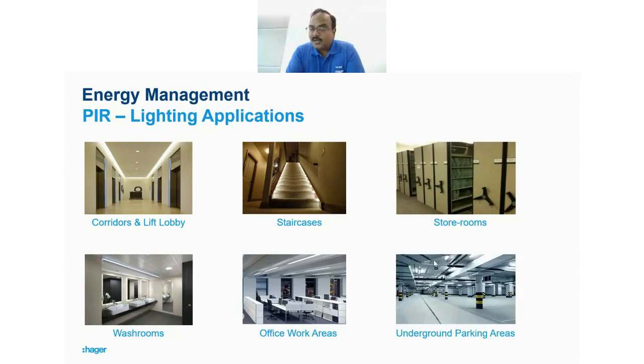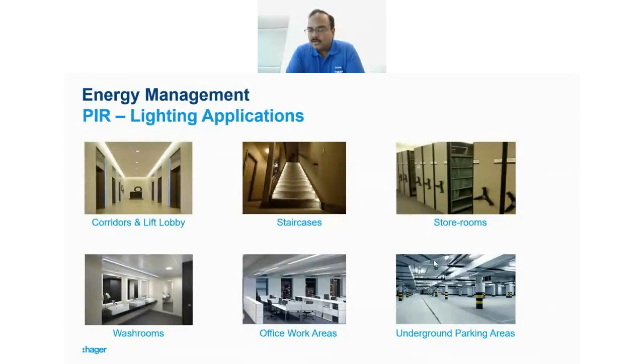Underground parking areas are also now using PIRs. One important note: because it's not a fully indoor environment, an IP rating of IP55 or above should be selected for motion detectors in these areas. This ensures the lamps in different sections are only activated when people walk through or cars come in.